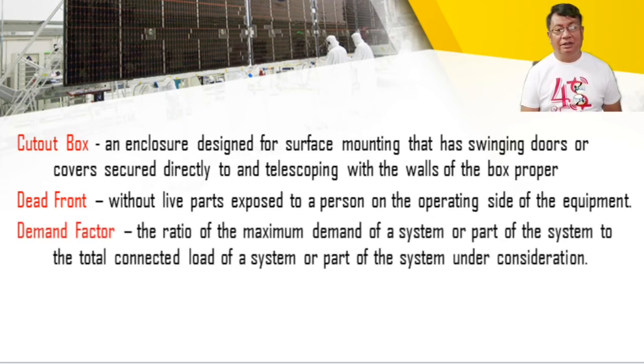We also have this demand factor. It is the ratio of the maximum demand of a system or part of the system to the total connected load of a system or part of the system under consideration. So the ratio of the maximum demand to the actual total connected load. This means that, for example, in a branch circuit we have 10 lamps, and we can say that not all 10 lamps will be lighted at the same time. So maybe we will reduce it to something like an 80% demand factor, because, as I said, it is a consideration that not all appliances or loads connected on that branch circuit will be used simultaneously or at the same time. So we have that demand factor.